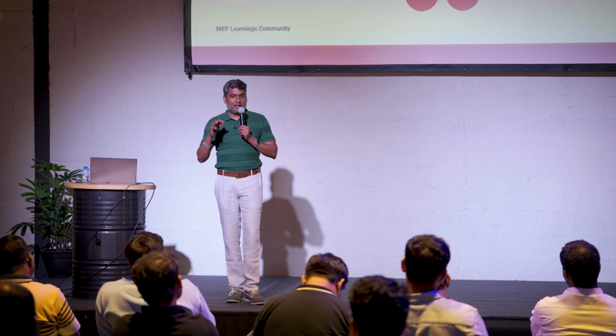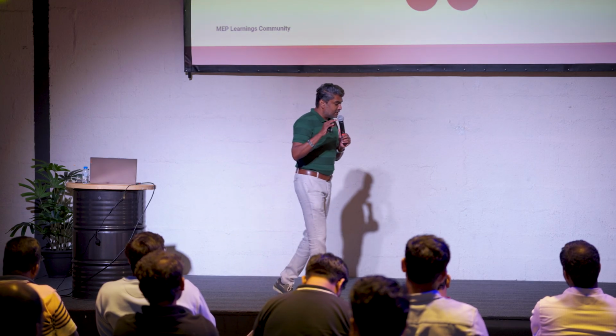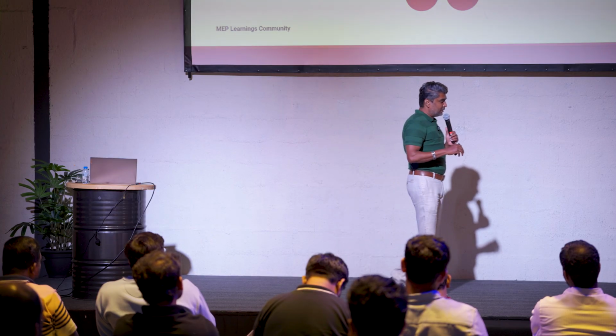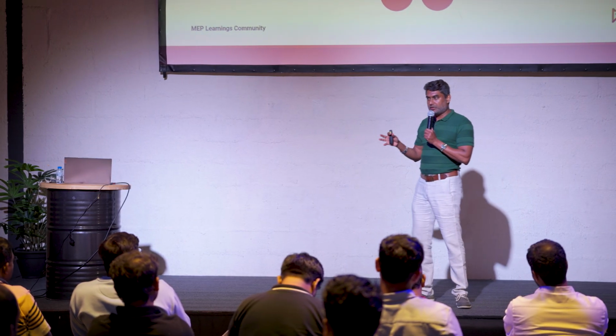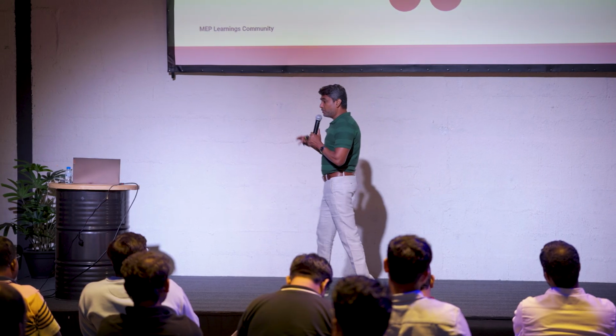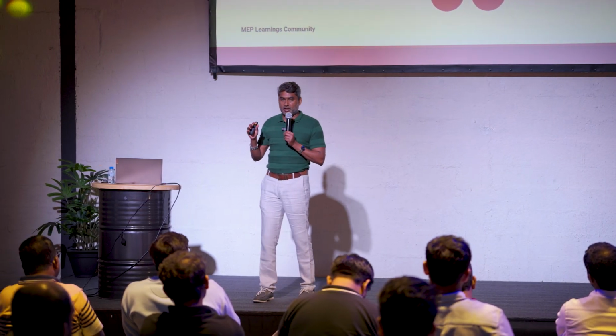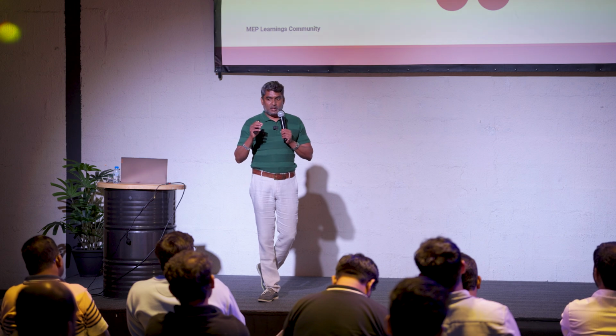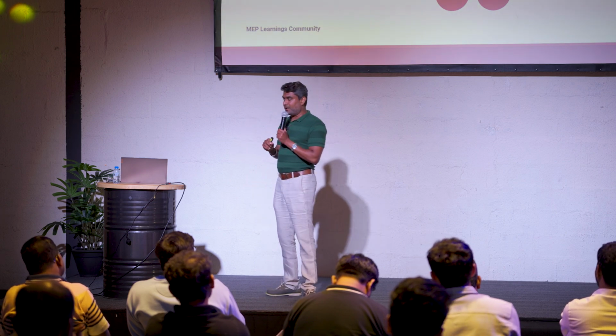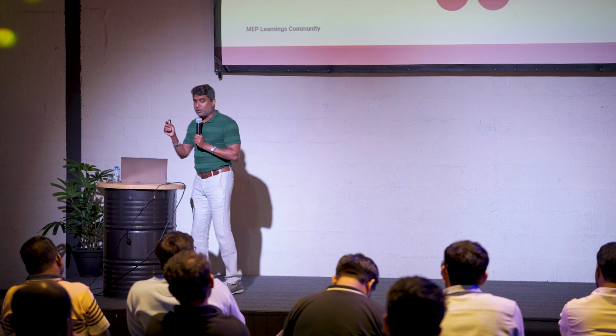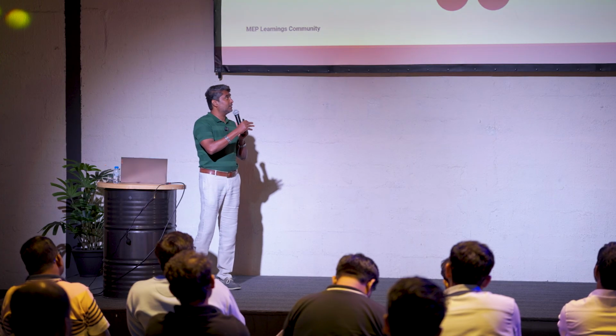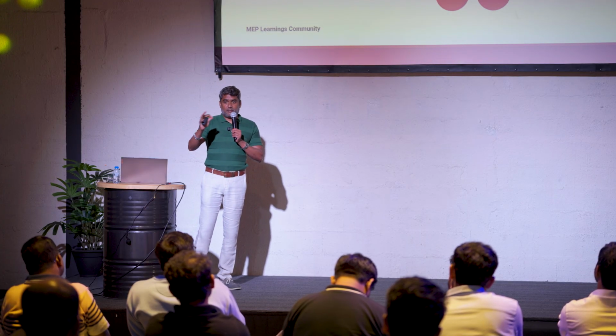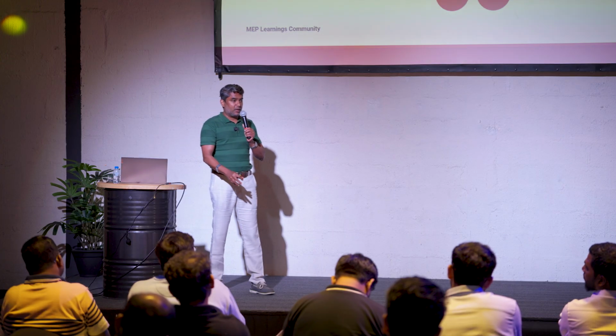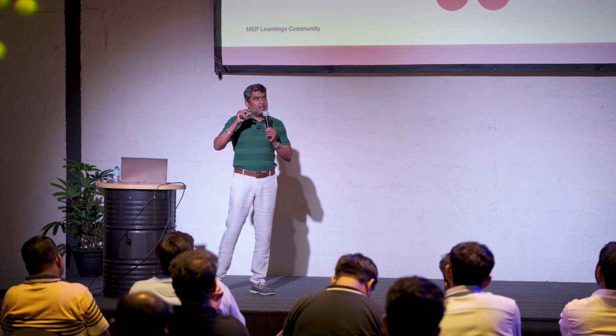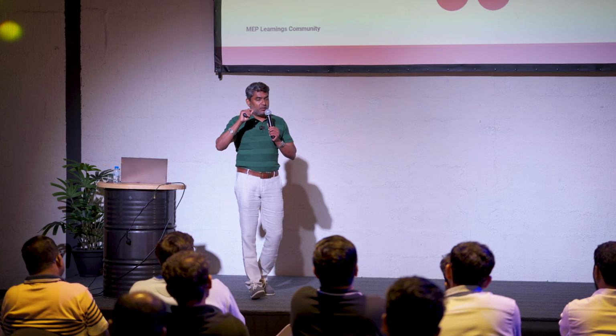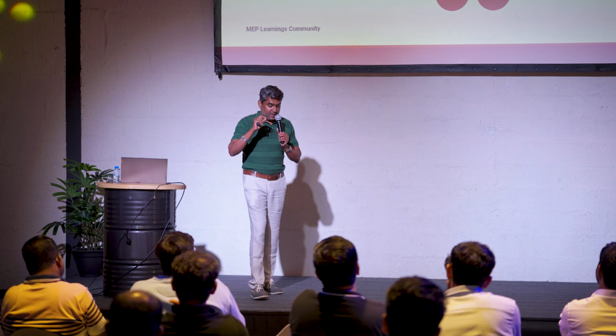Exactly. Again, we have to safely evacuate the people. Statistics says that people in a fire-affected building don't actually die because of the fire burns. Most of the people die because of the smoke actually. So it is of paramount importance that you clear the smoke in all the escape routes. That's the reason all the smoke extract fans will have to be notified that there is a fire on the floor. Specifically, the notification will have to go like this: this floor is on fire.